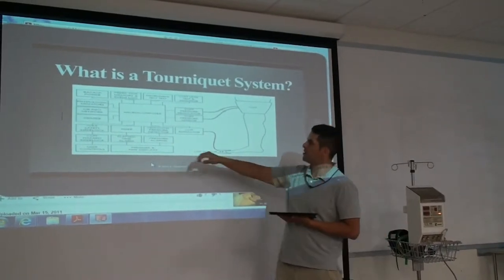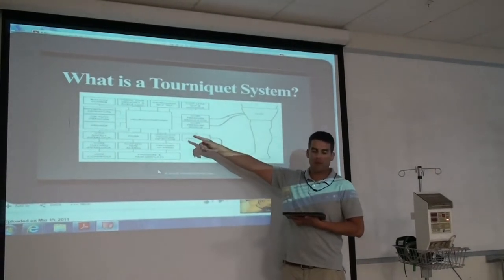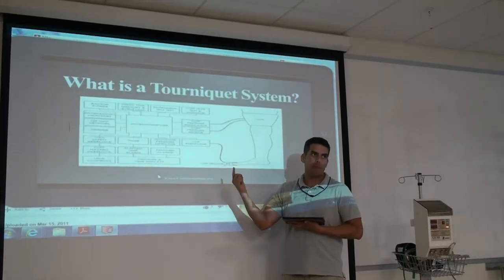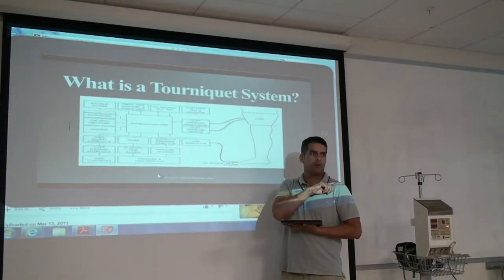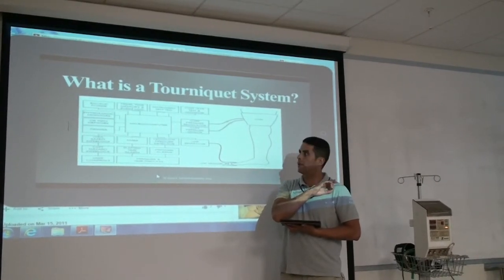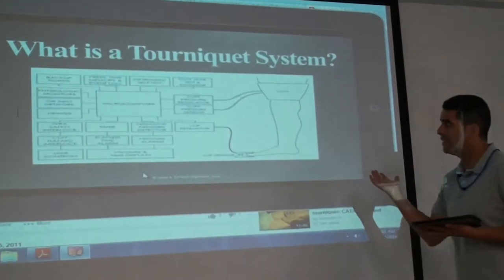They analyze the pressure that they have and they set up the set points in the microcontrollers and they release pressure through a pump to the parameters that the surgeon or the medical practitioner set up for the patient. Simple like that.